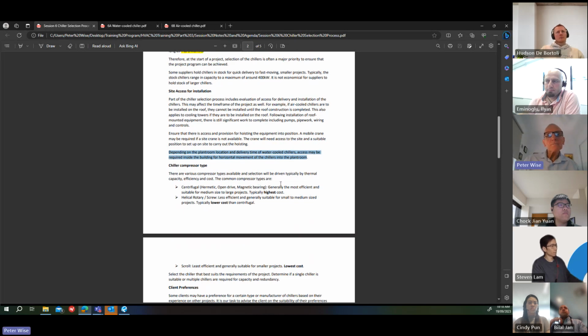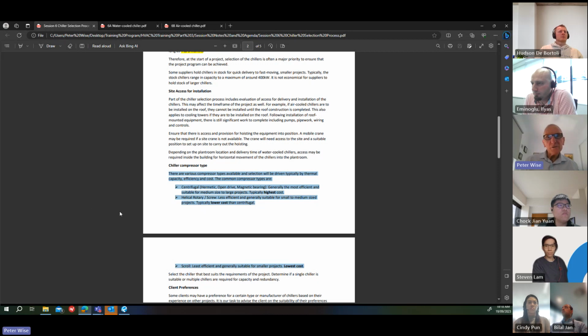Now, compressor types. There are various types of compressors available. And selection will be driven typically by the capacity, the efficiency required, and the cost. As I said before, efficiency and cost go together. If you increase the efficiency, normally you're going to push the cost up and you're going to go to a different compressor type. So the most common types are centrifugal, can be hermetic, open drive, magnetic bearings, generally the most efficient and suitable for medium-sized to large projects, and typically the highest cost. So we'll just have a look at some examples of that.